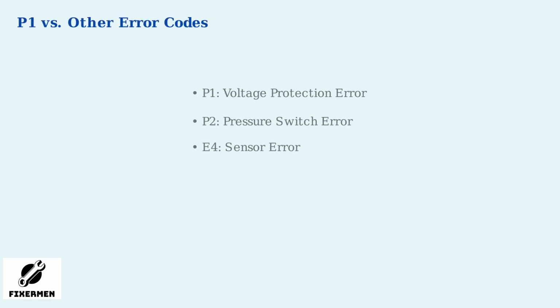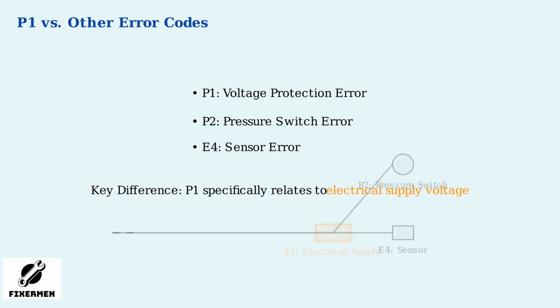HVAC systems can display various error codes, and it's easy to confuse P1 with similar codes. P1, the voltage protection error, specifically indicates issues with electrical supply voltage. This differs from P2, which relates to pressure switches monitoring refrigerant pressure, or E4, which signals sensor calibration or fault problems. The key difference is that P1 focuses on electrical voltage problems. If you're seeing consistent P1 errors, it's unlikely to be caused by refrigerant pressure issues like those in P2 or sensor calibration problems like those in E4. Instead, P1 points to faults in the electrical components and power supply.